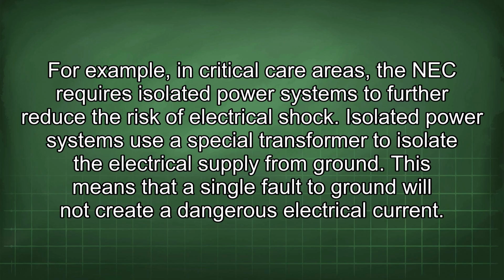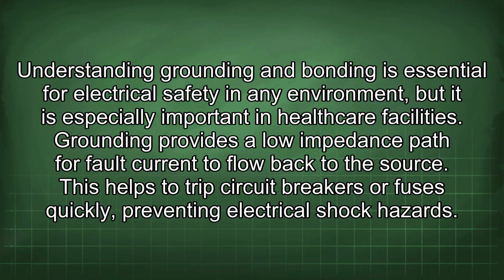For example, in critical care areas, the NEC requires isolated power systems to further reduce the risk of electrical shock. Isolated power systems use a special transformer to isolate the electrical supply from ground. This means that a single fault to ground will not create a dangerous electrical current. Understanding grounding and bonding is essential for electrical safety in any environment, but it is especially important in healthcare facilities. Grounding provides a low impedance path for fault current to flow back to the source. This helps to trip circuit breakers or fuses quickly, preventing electrical shock hazards.